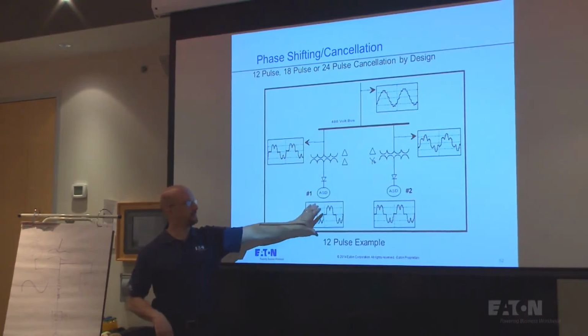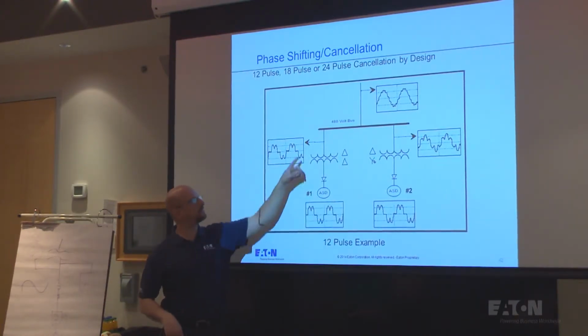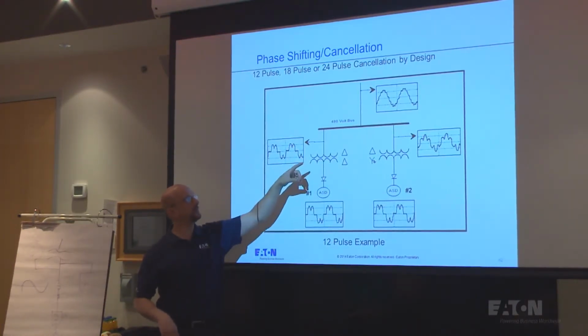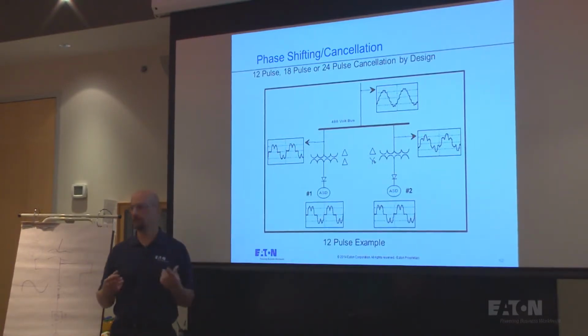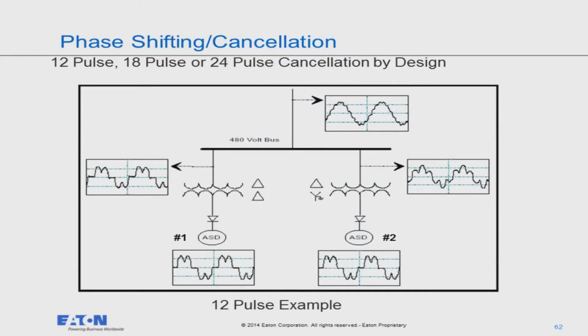What if this one does 5 amps and 10 amps? Now instead of being 15 amps, it's actually 10 minus 5 or 5 amps left. So I've reduced my harmonic current substantially. So any phase shifting is better than none, is the point. You can do that with individual drives. You can do it with a whole MCC.